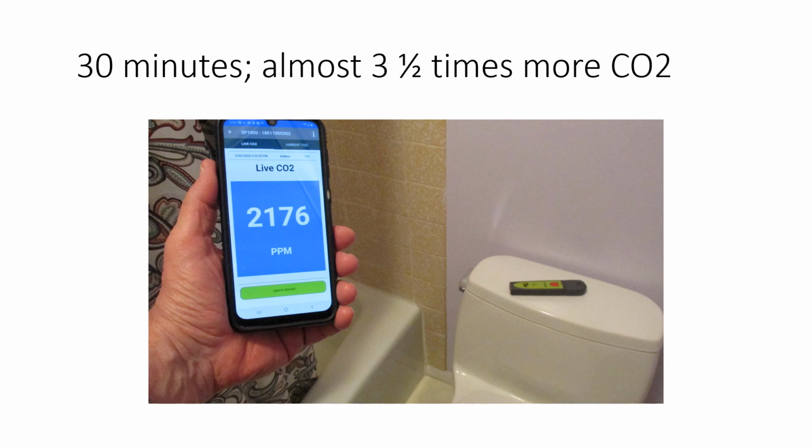Think of a house. Think of a room. Think of a restaurant. Think of a classroom. I have measured CO2 in my classrooms for decades. Every time I'm in front of an audience, I need to know if it's at this level, 2,176 parts per million after 30 minutes. We're turning on ventilation or we're taking more breaks. The last thing I want is people falling asleep in my seminars.